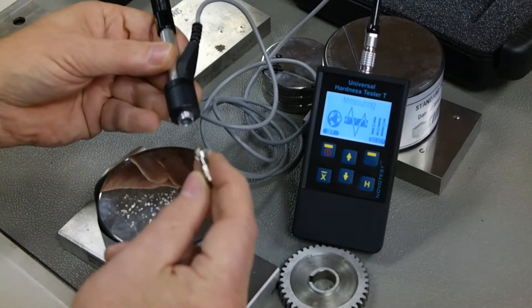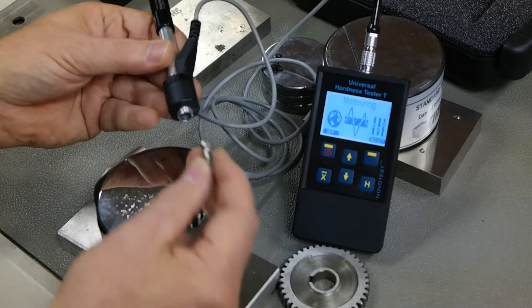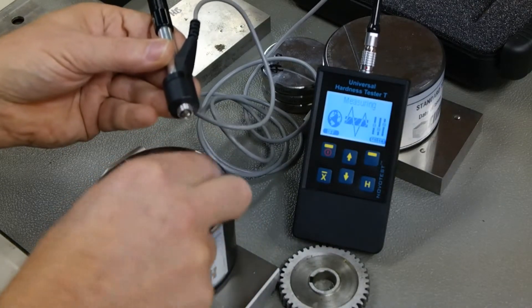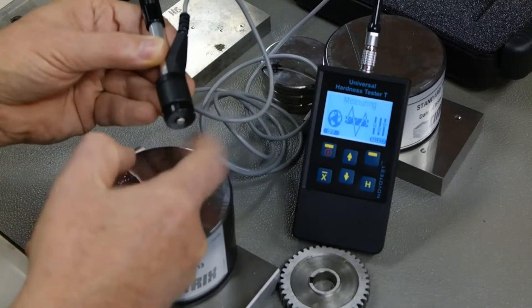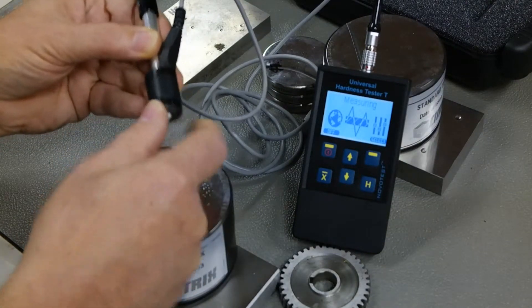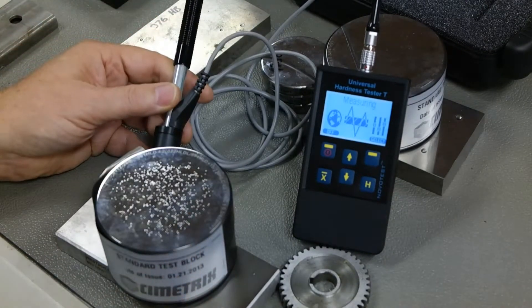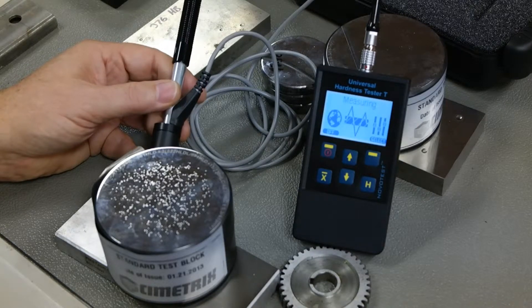The other thing that we can do with this device, because the impact body inside is very highly precision machined, and the calculations that are done based on this bouncing off the part, we can set up calibrations for this for different material types, which we have now done with the unit. So it mirrors what can be done with stand-alone rebound hardness testers.